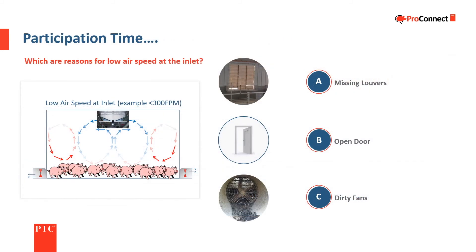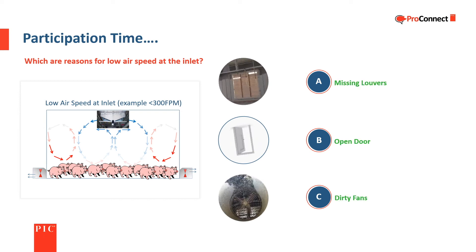Now time for a little participation. What are reasons for low airspeed at the inlets? Missing louvers, open door, or dirty fans? All three can be reasons for low inlet airspeed.